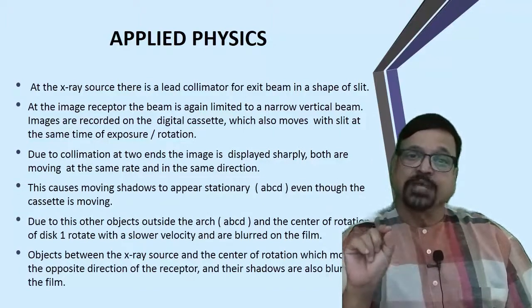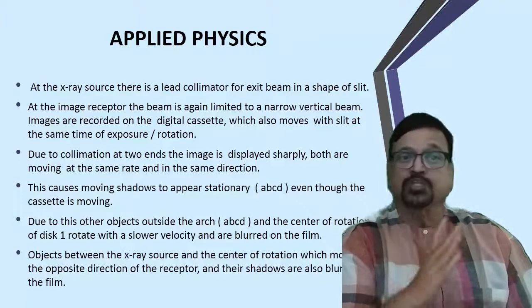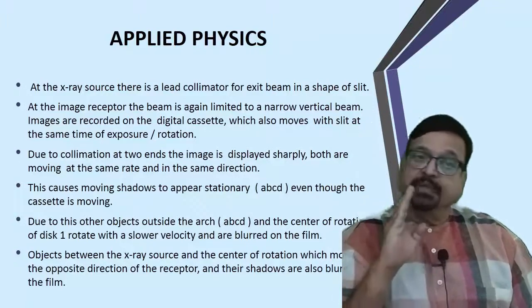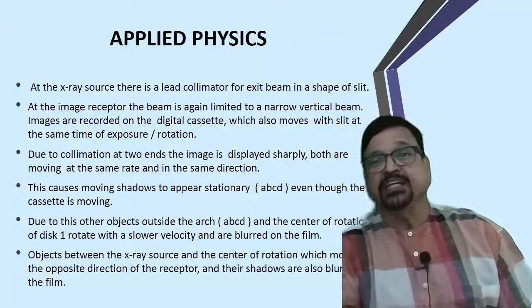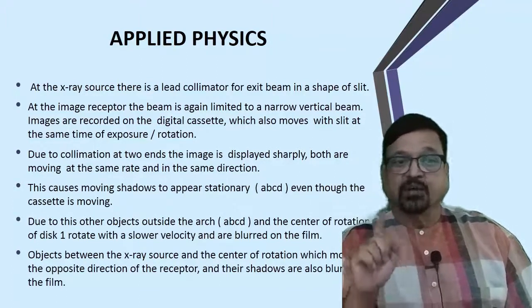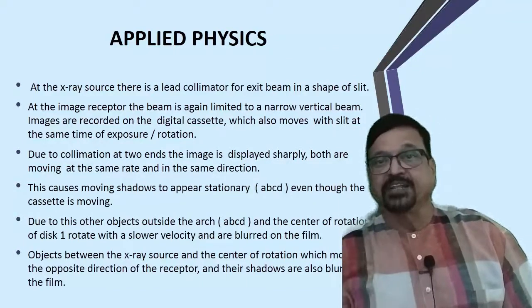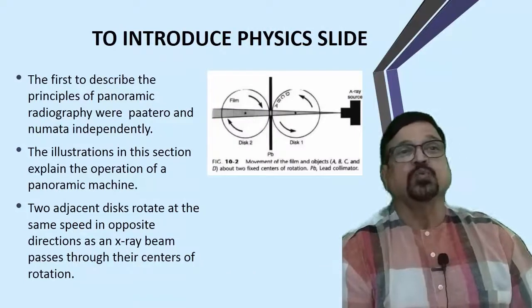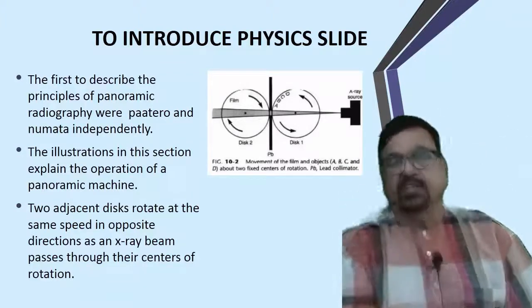To understand this, consider an illustrative diagram in which objects A, B, C, D are marked as the objects to be radiographed. Due to other objects outside the A-B-C-D arch - possibly at the center of rotation - the movement is not at the same speed as objects A, B, C, D. So only A, B, C, D will be clearly focused. Objects between the X-ray source and the center of rotation, as well as objects in the background that move in the opposite direction, will have blurred shadows.